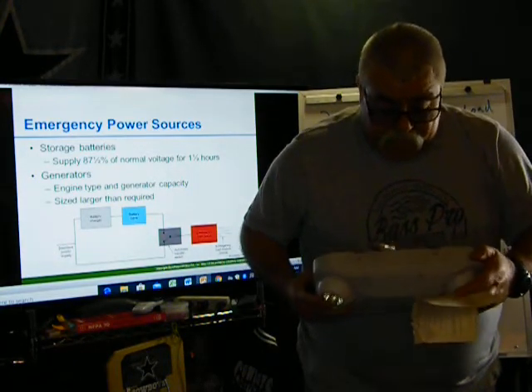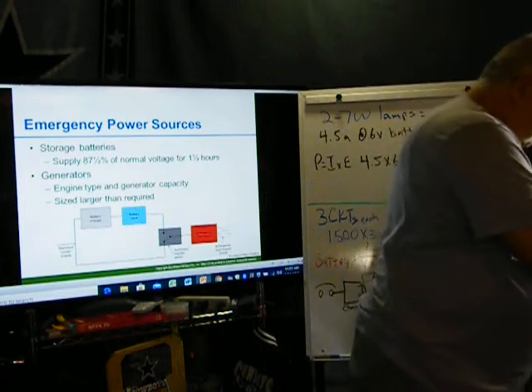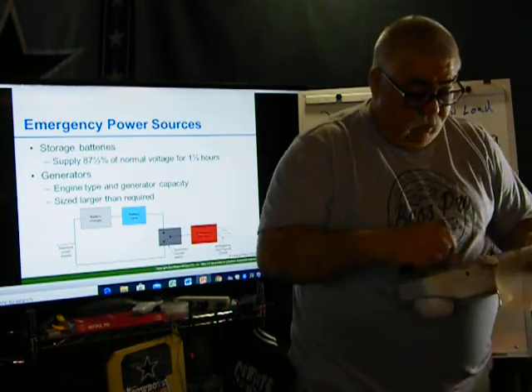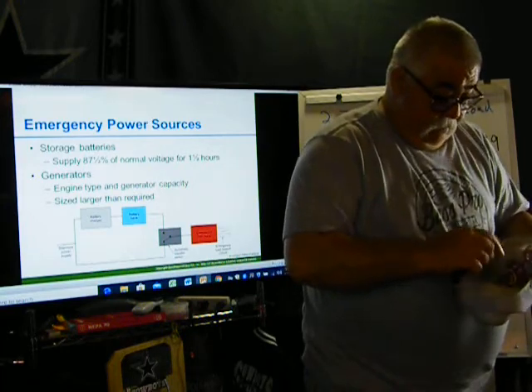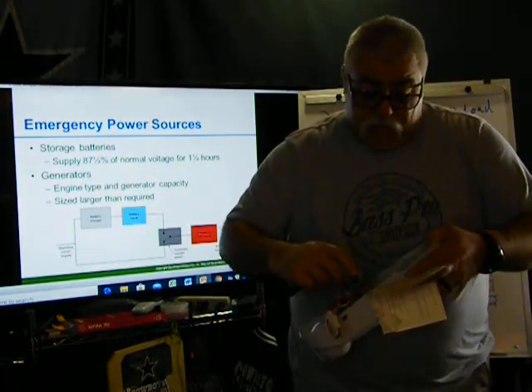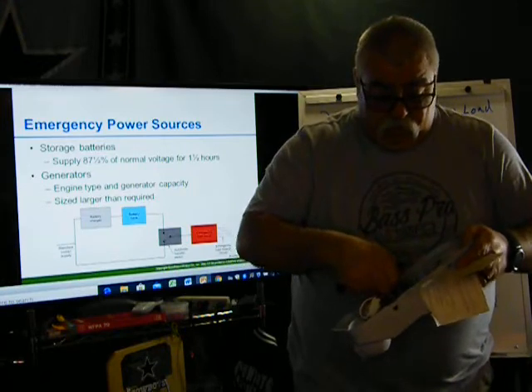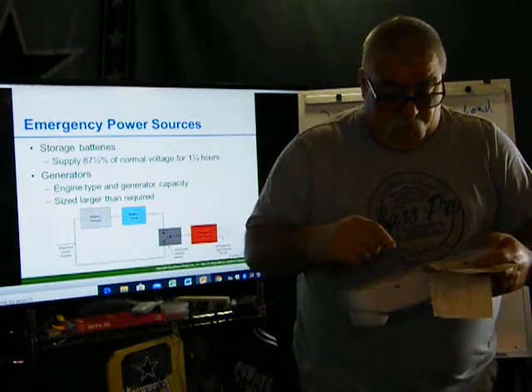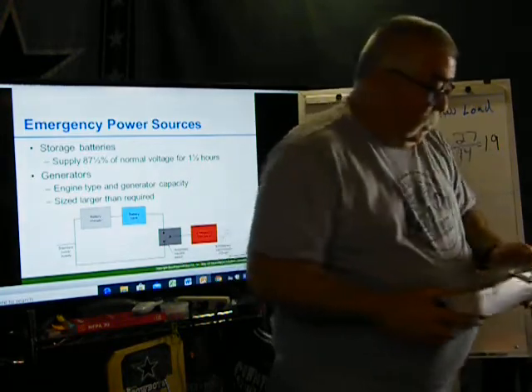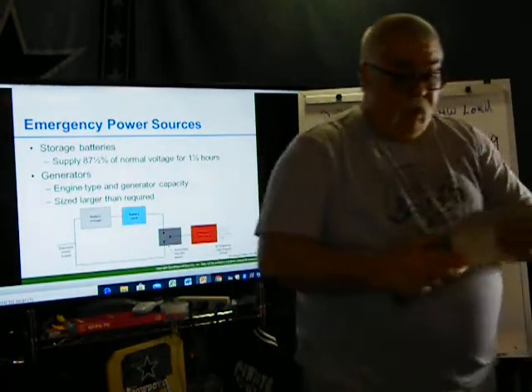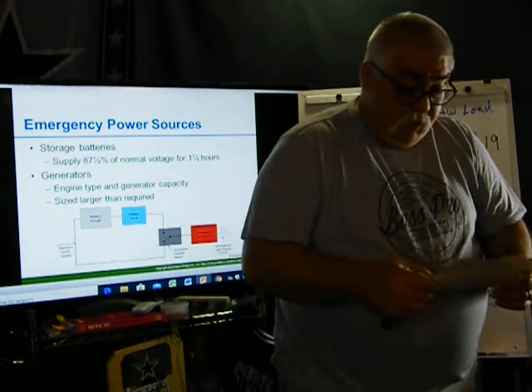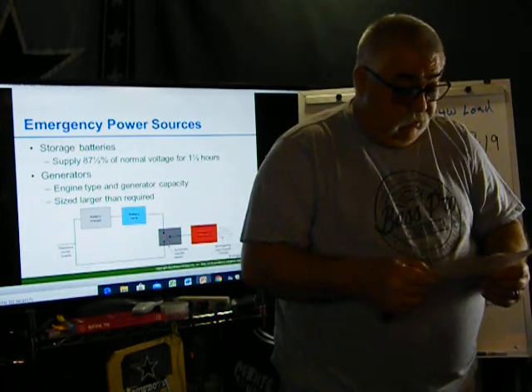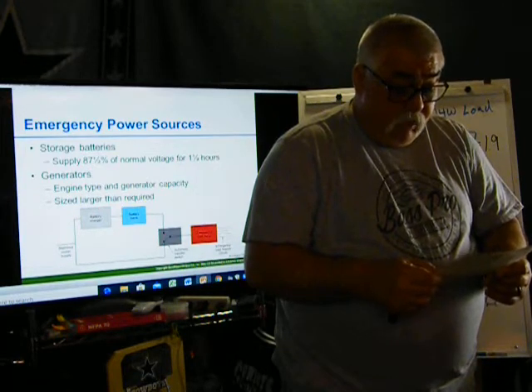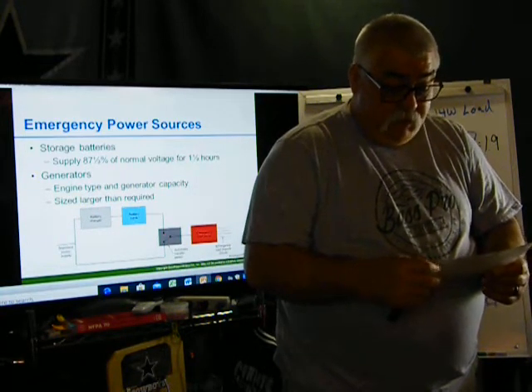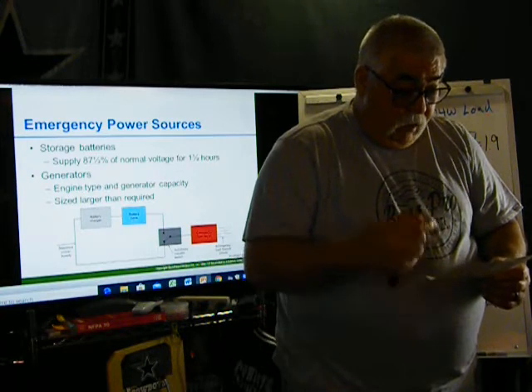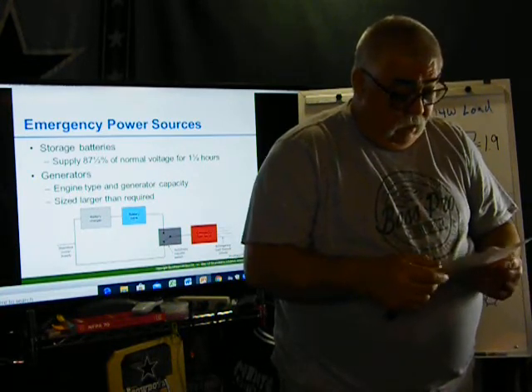That's the test button. And when you push the test button, what it does is it goes inside and it turns this on. I got it taken apart right now. But the test button, here's the test button. Pushes that in. The board goes across here. Pushes that in, and the lights come on. So, according to the manufacturers, it says maintenance. This equipment is fully automatic and battery is sealed and lead acid type. No maintenance is necessary. To operate, once you hook it up, the battery will let it charge 24 hours.